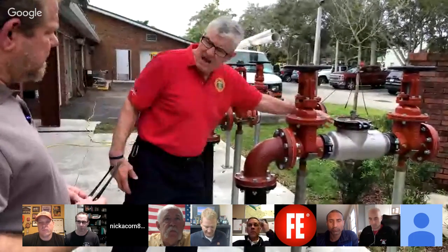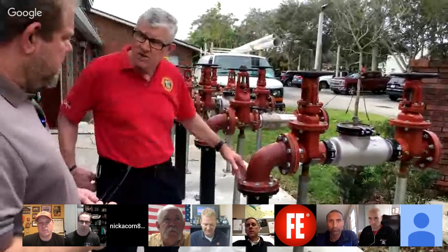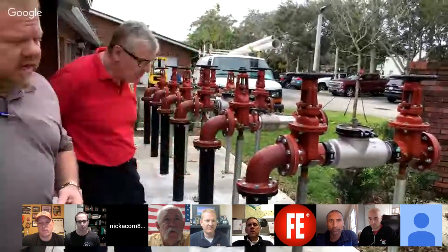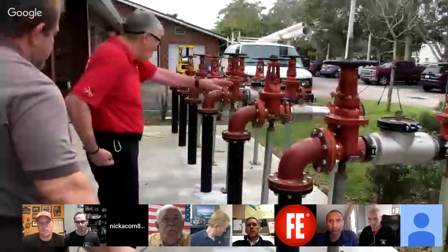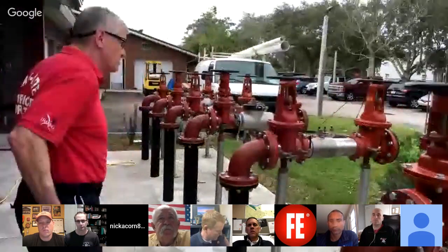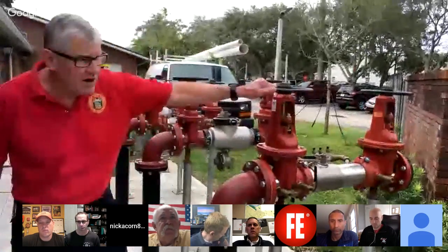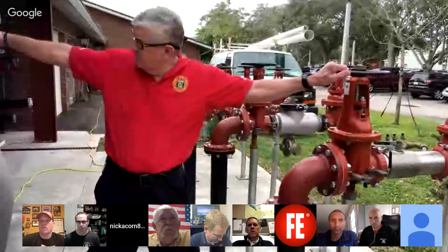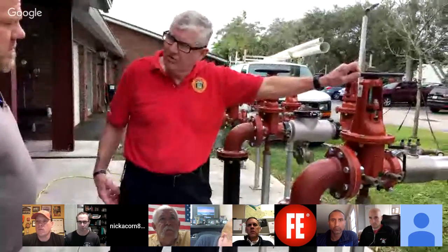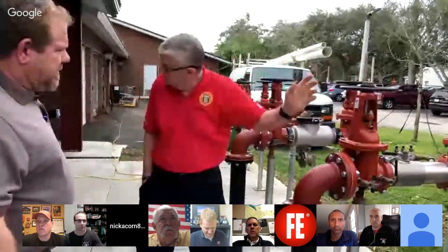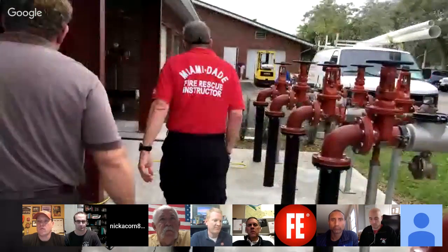But if we did that, we'd still have the fire department connection we could pump in. Yes, exactly. All right, so these are all backflow prevention devices. Again, 3 different types. Mr. Collier, if we close this down and we leave the fire pump running, we run a risk of burning up the fire pump. Absolutely, no water supply. Okay. All right, let's take a walk over here.